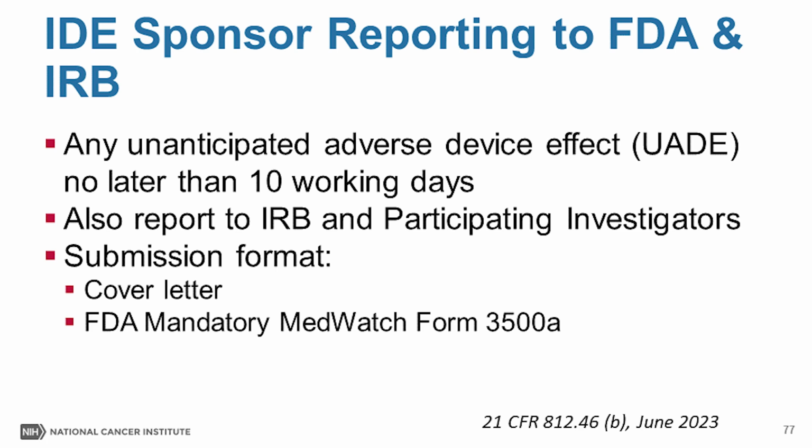The submission should include a cover letter summarizing the sponsor's analysis of the event and the FDA's mandatory MedWatch form, that 3500A. The sponsor should submit additional reports, obviously, concerning the effect as appropriate or as requested by the FDA.